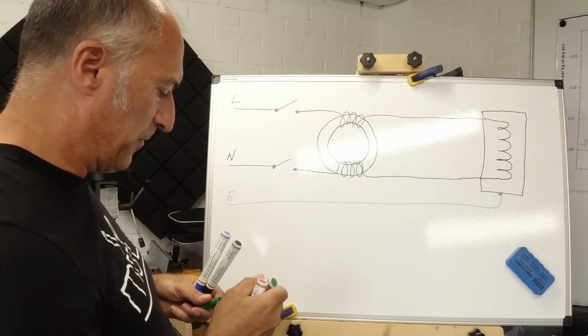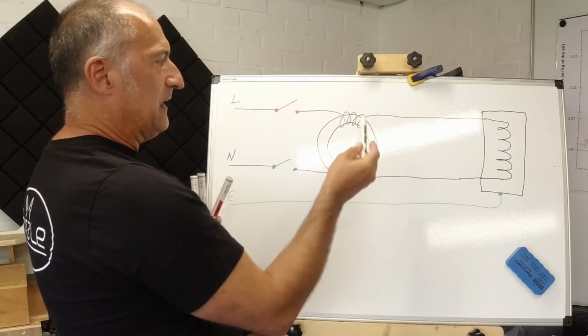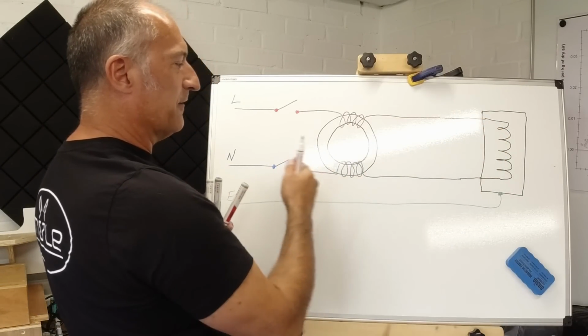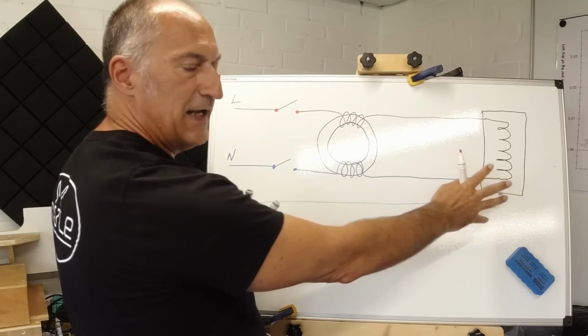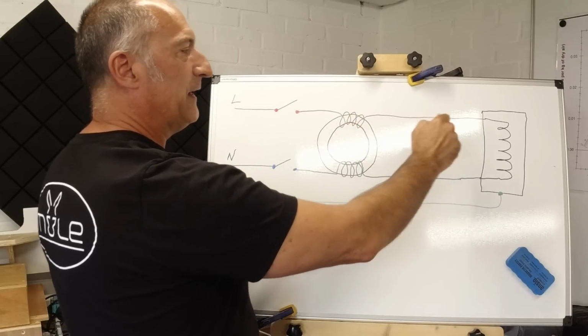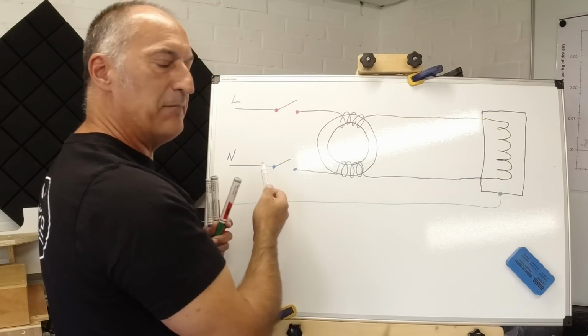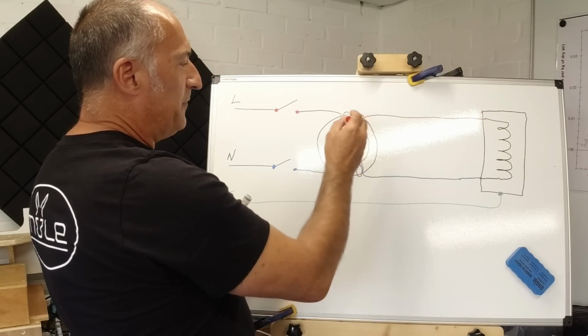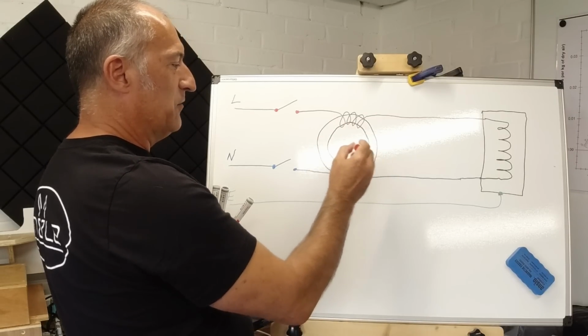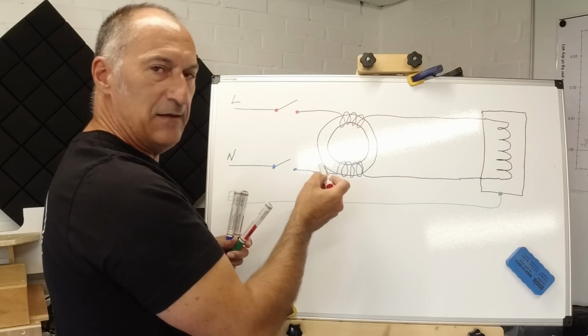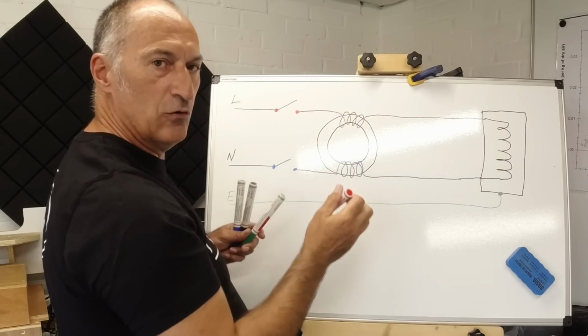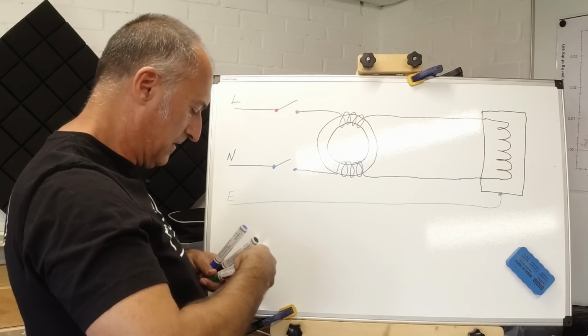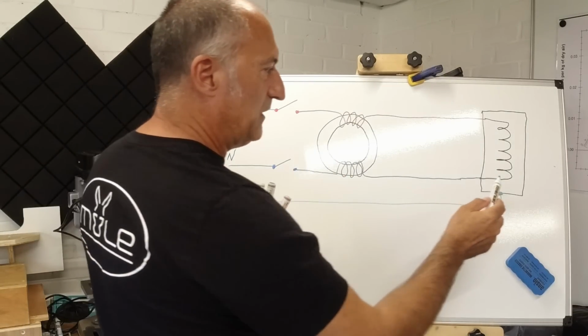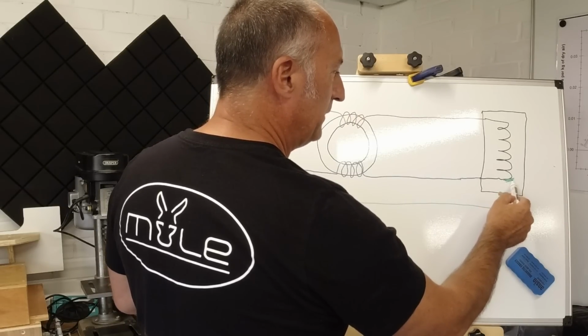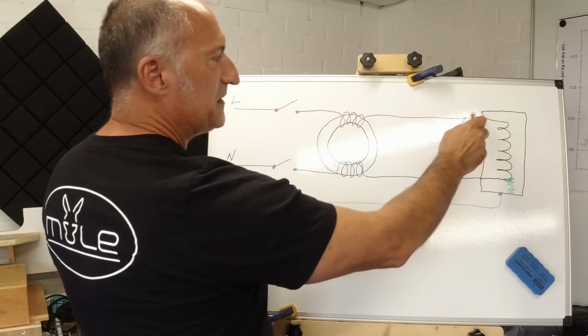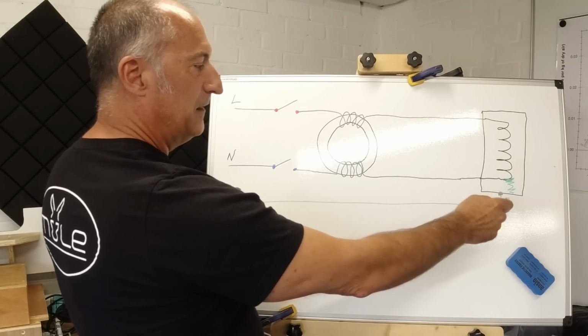So during normal operation, the RCD is monitoring the flow of current within this circuit, and if everything's okay and the appliance is working okay, the current flowing down the line will be exactly the same as the current coming back on the neutral. And what happens in this coil is you get a magnetic field built up, and because the current flow is the same, the magnetic field on the line and neutral will cancel each other out. Now what happens if for some reason we have a fault in the appliance, so we have a fault to earth? Some of this current is going to leak out of the device and back down the earth.